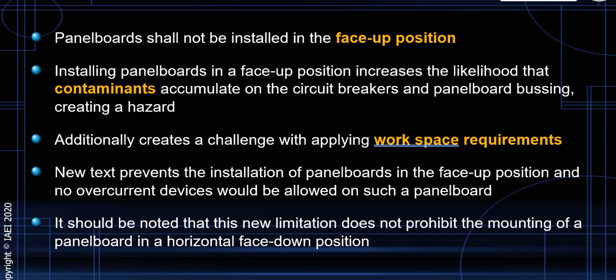So let me show you. Now, if we look at Article 408.43, panel boards shall not be installed in the face-up position. That's a '23 slide. That's from the changes from the 2023 edition of the NEC. So installing panel boards in a face-up position increases the likelihood that contaminants accumulate on the circuit breakers and panel board bussing, creating a hazard, obviously.